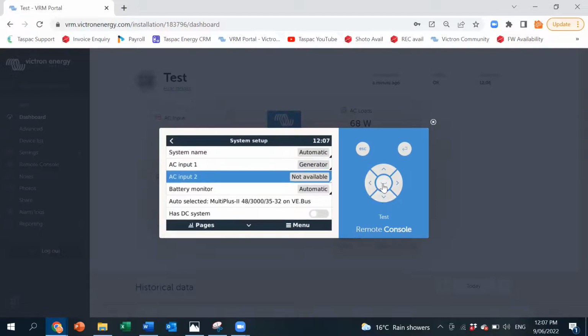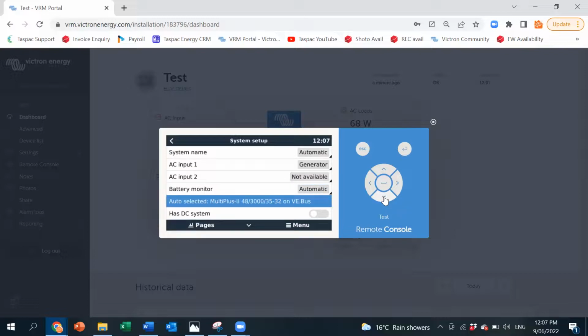AC2 input, well, that's not actually available. We don't have two AC inputs on this inverter. If it was a Quattro, we would have two AC inputs. You could have one as the grid, one as a generator, or you could have both as generators and have two generator inlets, one for a big generator that you normally use, and then maybe one set up for a 10 amp generator that you might hire if the big one dies.